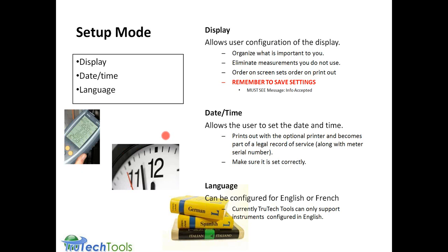And once you've selected your changes and your display order and the parameters you're measuring, you just have to be sure to remember to scroll down to the very bottom where it will say save settings, and you press and enable it to save settings, and at the top across the screen it will say info accepted. Only when it says that have you made the changes. If you don't have that message coming back to you, you haven't made any changes on the meter.